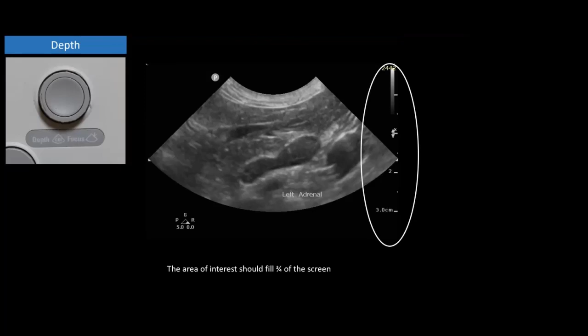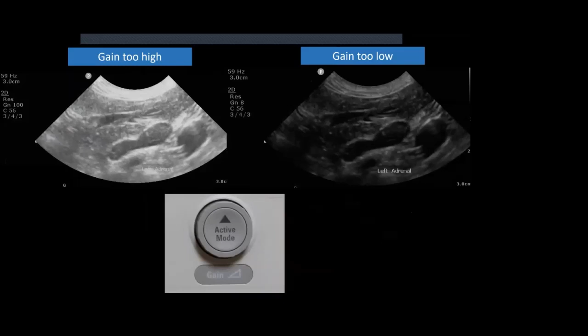The next button to think about is your gain. And the gain you want to set so that it's not too high like this. That's a very snowy image. And you don't want to have your gain too low so that it's very dark. So it's just a case of adjusting your gain to get it right for your own eye. The next thing to think about of the 4 magic buttons is the time gain compensation.